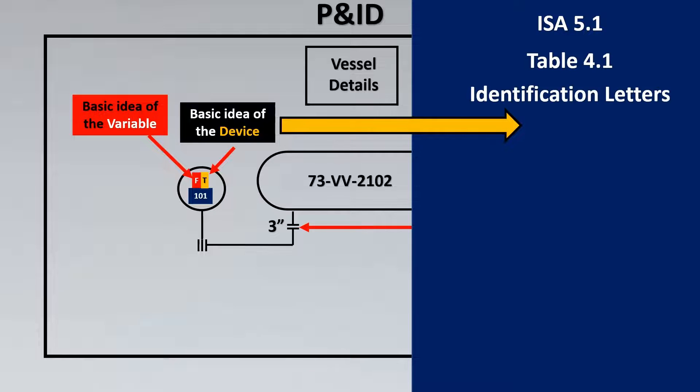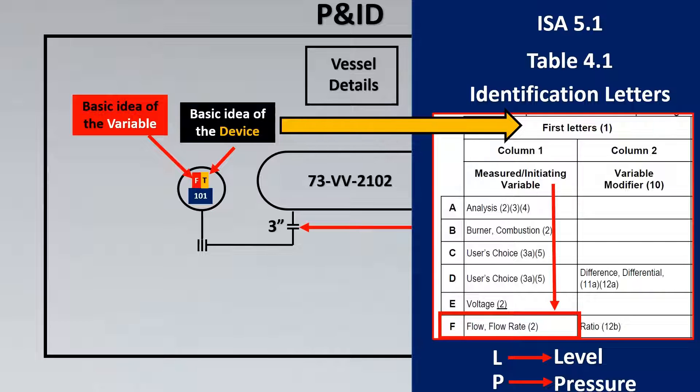For example, let's try to look from ISA perspective that what are these letters standing for. So ISA 5.1 has a table 4.1 which has identification letters for each of these cases. So for example, let's take a small snippet from that. So here's F standing for flow. Similarly you would have L which is standing for level, P which is standing for pressure, T standing for temperature, etc.